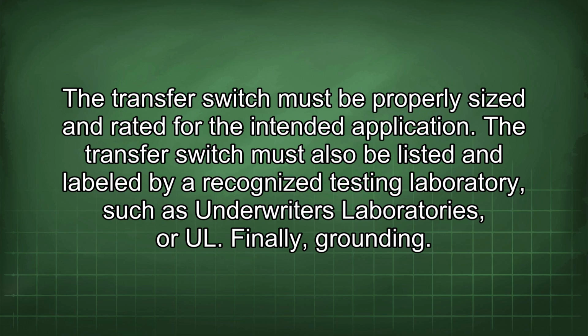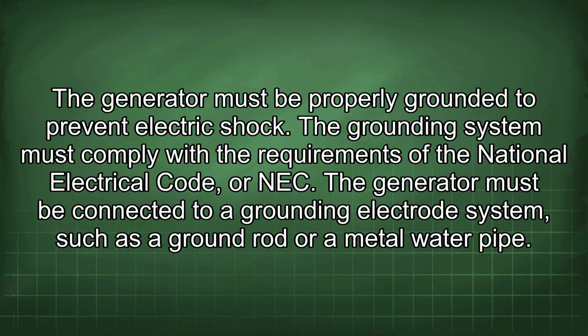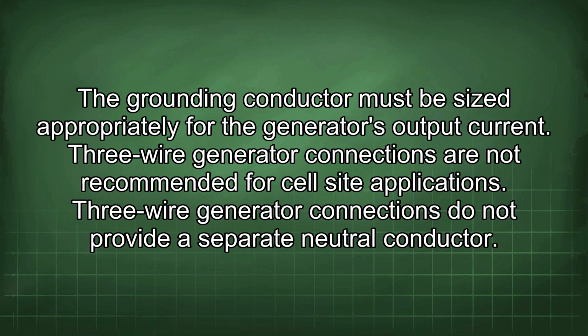Finally, grounding. The generator must be properly grounded to prevent electric shock. The grounding system must comply with the requirements of the National Electrical Code, or NEC. The generator must be connected to a grounding electrode system, such as a ground rod or a metal water pipe. The grounding conductor must be sized appropriately for the generator's output current.